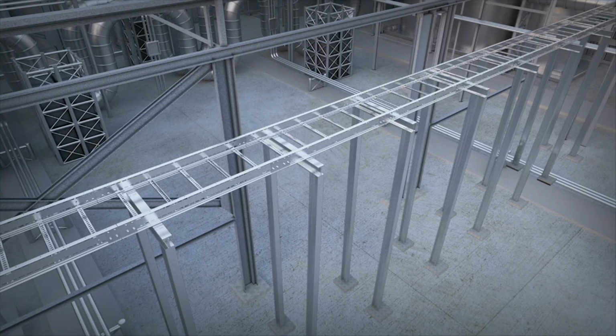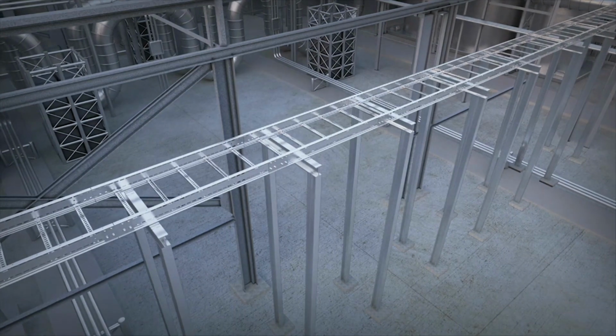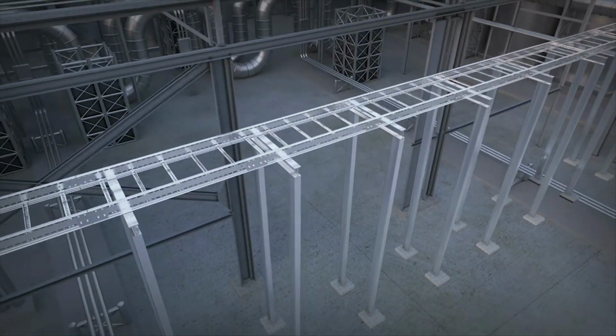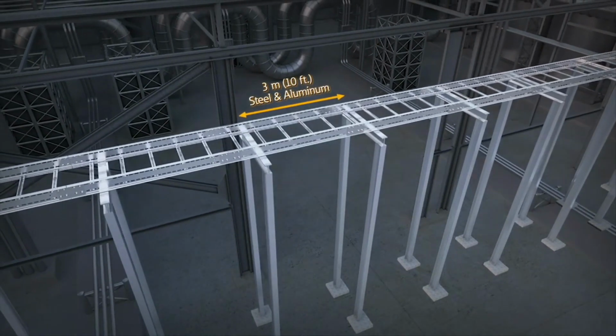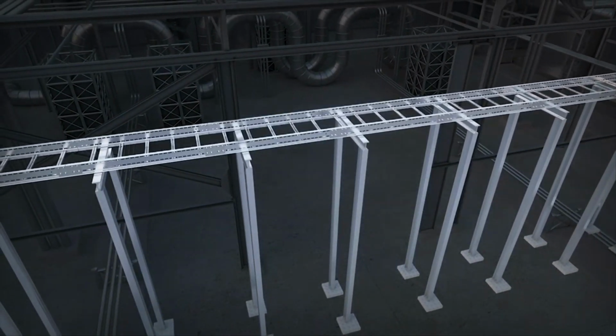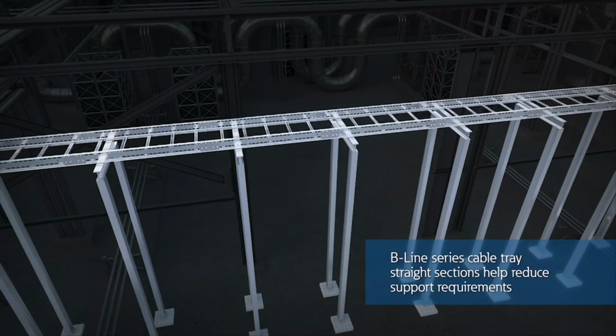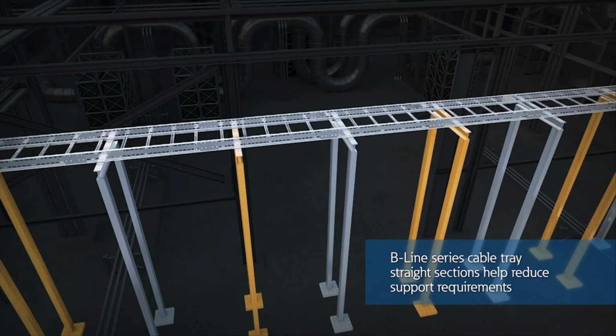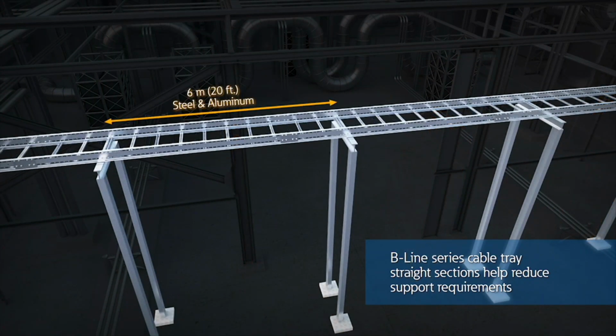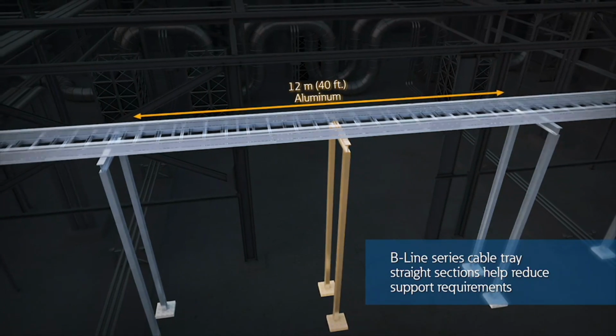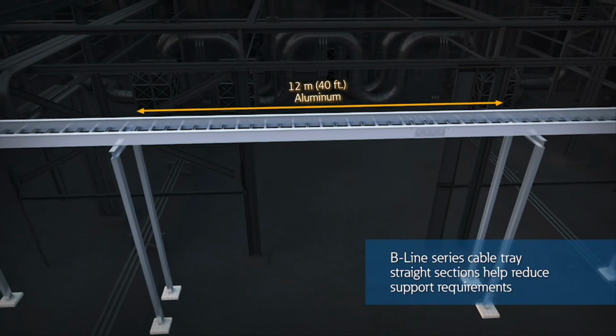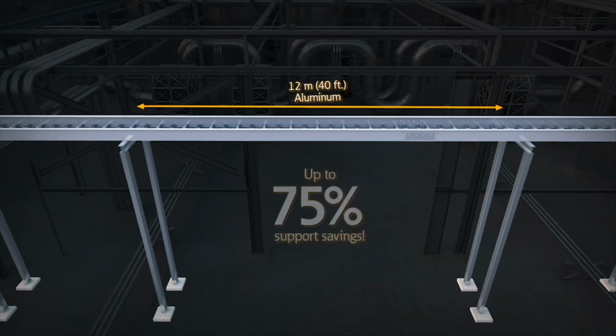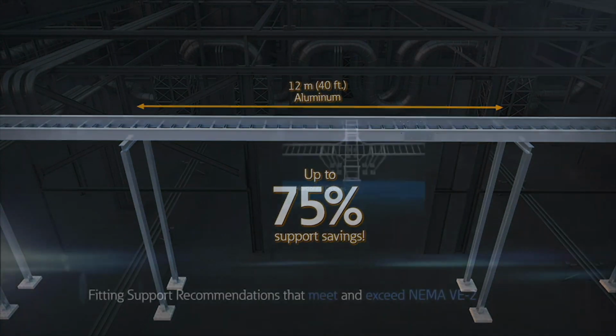To help explain how this works, let's take a closer look at some key installation methods, starting with cable ladder straight sections. Traditionally, the industry's minimal support span interval is 3 meters. However, through Eaton's engineered I-beam design, the B-Line series straight sections allow for the structural supports to be spaced up to 6 meters with steel cable ladder and up to 12 meters with aluminum cable ladder, reducing the number of required supports by up to 75%.